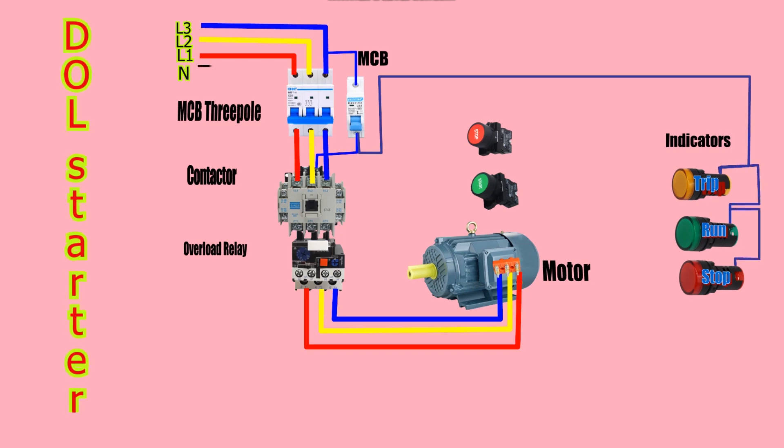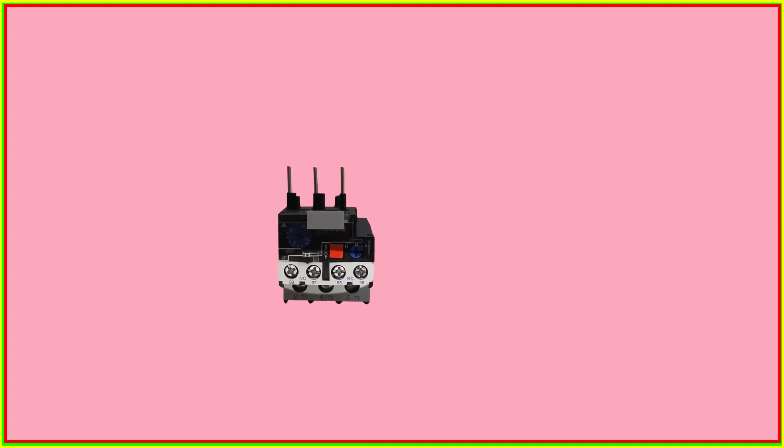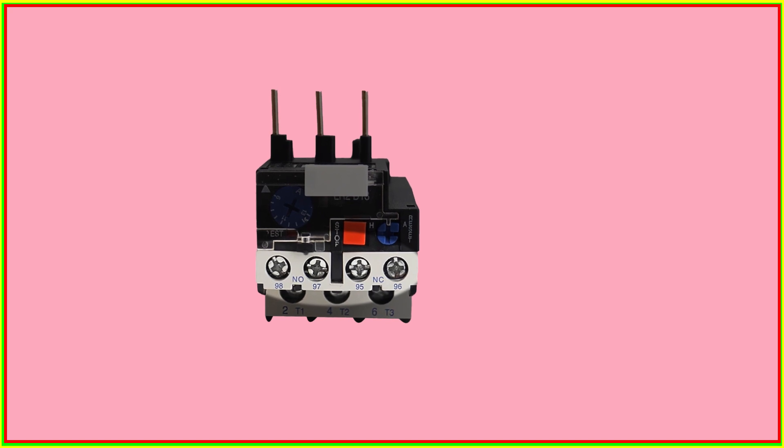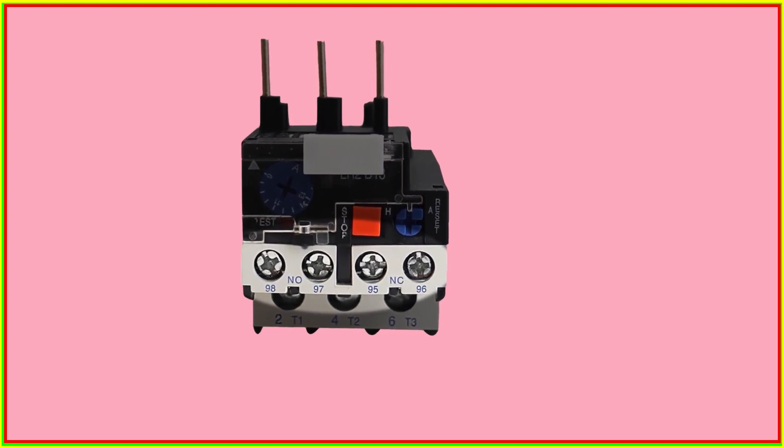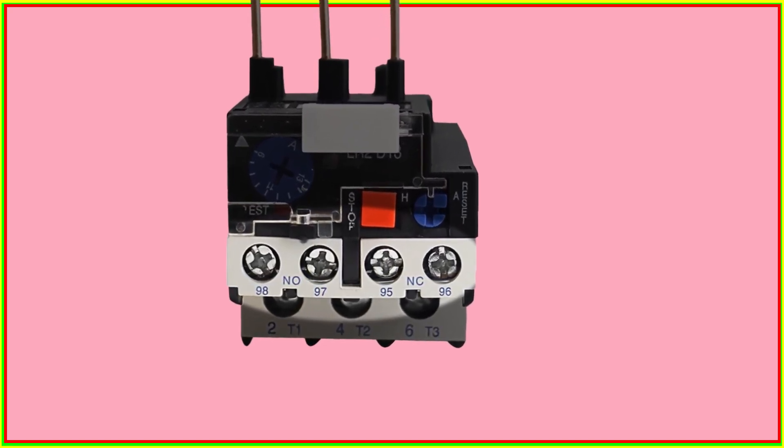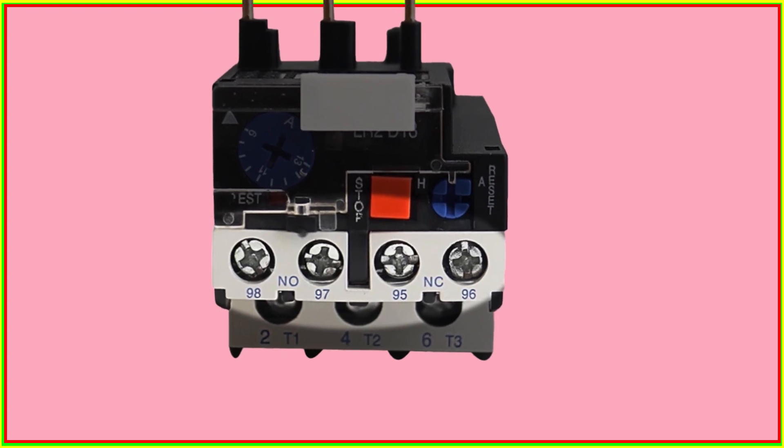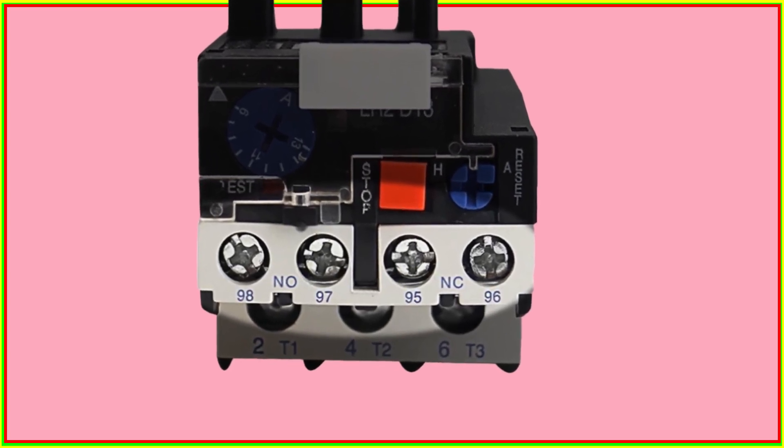In this DOL Starter, the neutral wire is connected to the normally open auxiliary contact of the magnetic contactor and looped with the normally closed contact of the magnetic contactor, the 98 and 95 contacts of the overload relay. The 98 is an auxiliary normally open contact of the overload relay with 97 contacts. 95 is the normally closed auxiliary contact of the overload relay with 96.